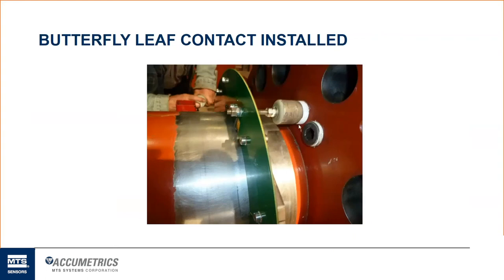We then will coat the threads with a special, this looks like Teflon tape. We've since gone to a special epoxy that has PTFE material embedded in it that we will coat those threads. And then we provide a seal washer on the end of the pipe thread piece to protect against any risk of hydrogen leak that comes out of that bore. We were approached by one of our OEMs many years ago that there was a very, very small chance that hydrogen could leak out. So we've gone the extra steps to prevent any of that. And we've actually had this whole assembly tested by a company, and it's able to withstand up to 20 PSI of gas leak pressure. And the spec was only to prevent 10 PSI. So it's more than capable of preventing any risk of leak of hydrogen into the exciter.